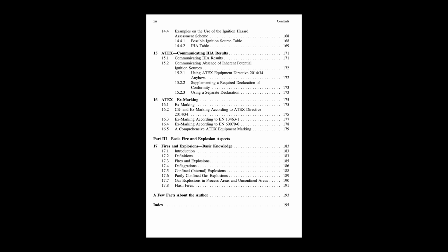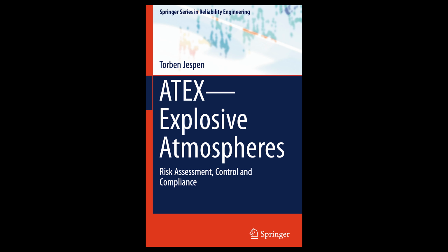Okay. This understanding of zoning leads logically to equipment selection and protection methods. What are the core principles when choosing equipment for these zones? The absolute core principle: select equipment that is specifically designed, tested, and certified as safe for the zone it's going into and for the type of explosive atmosphere present, gas, vapor or dust. Can't just use standard industrial gear.